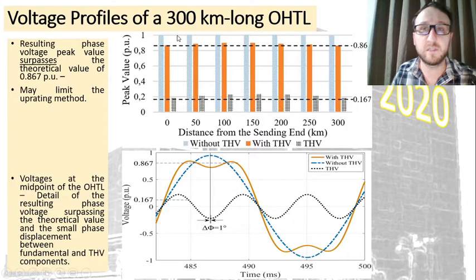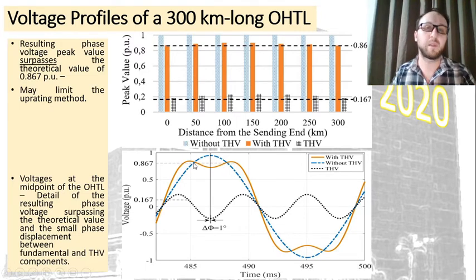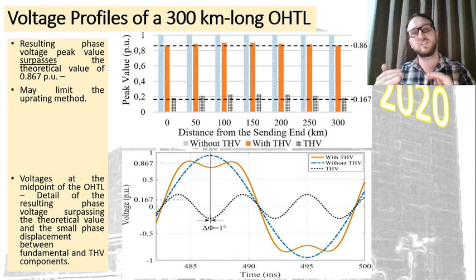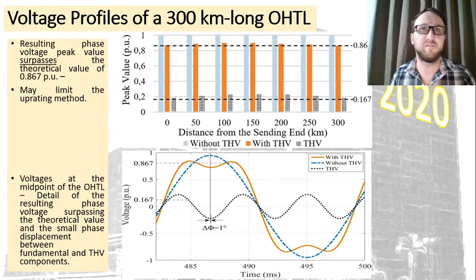Repeating for 300 kilometers, we have this voltage, and we are just focused on the orange bars, and they slightly surpass this voltage limit, but it's not a problem because for any system we have some voltage limits, and more than 5 or even 10% is acceptable depending on the case, but considering about 5% is okay. So our resulting voltage here would be acceptable.